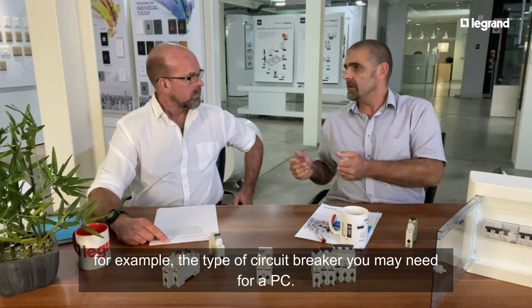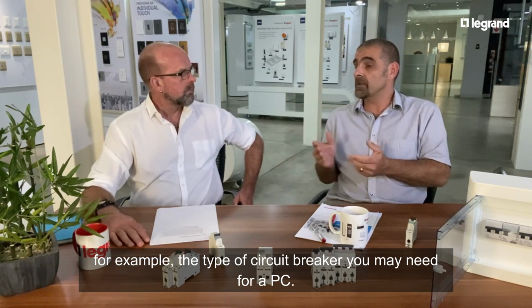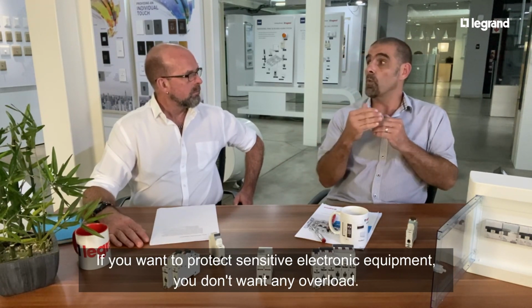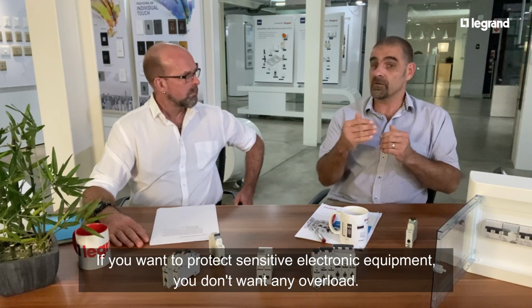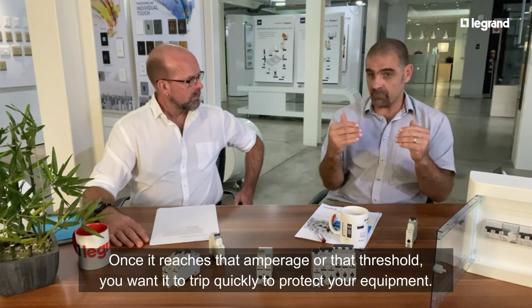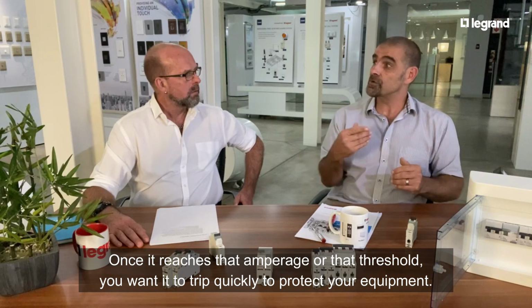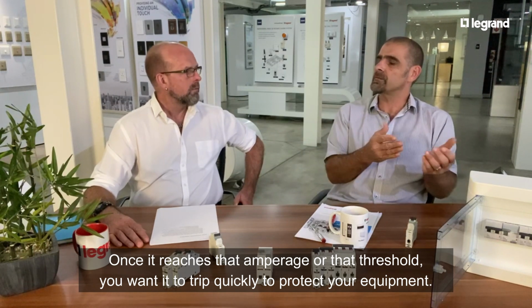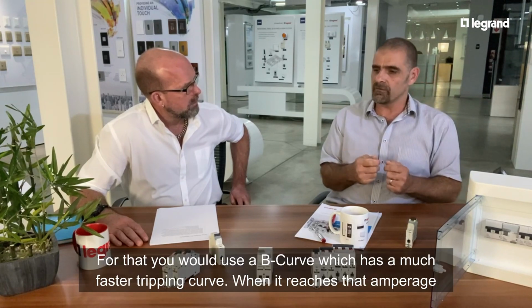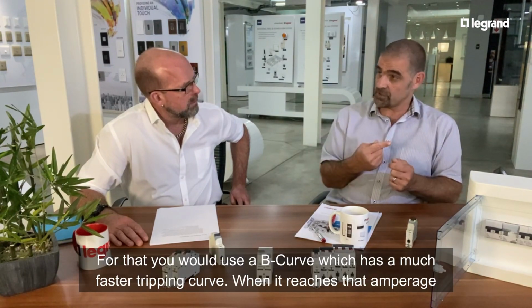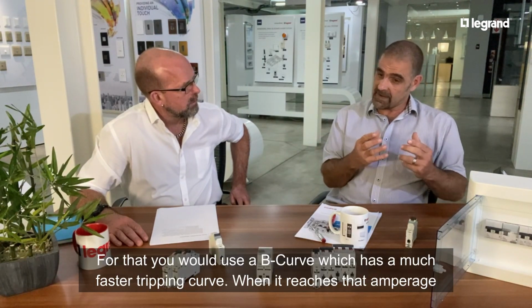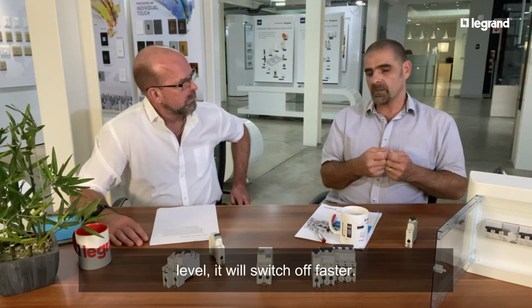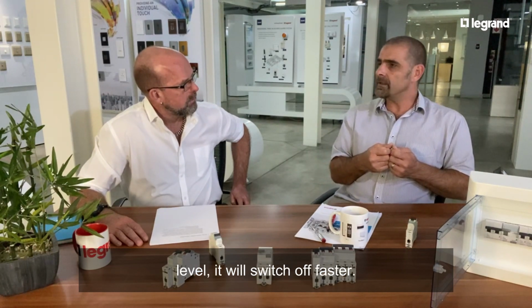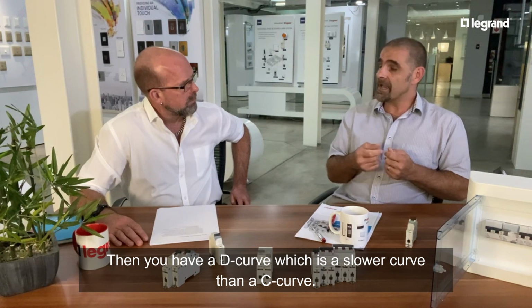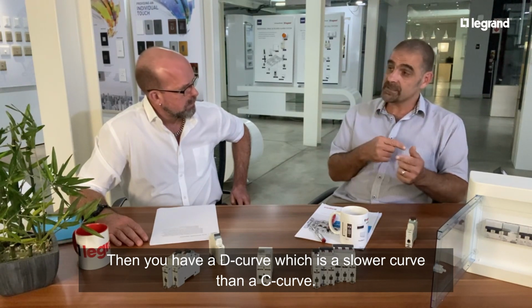If you want to protect sensitive electronic equipment and you don't want any overload, and you want it, once it reaches that amperage or that threshold, to trip quickly to protect your equipment, especially electronic equipment, you would use a B curve, which has a much faster tripping curve. When it reaches that amps, it will switch off faster. Then you've got a D curve, which is a slower curve than C.